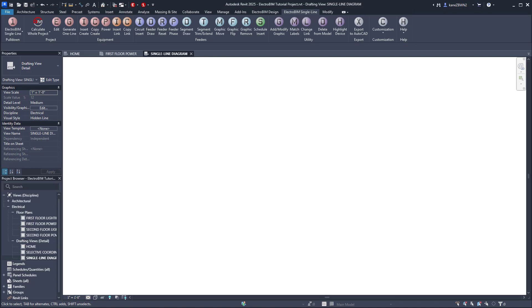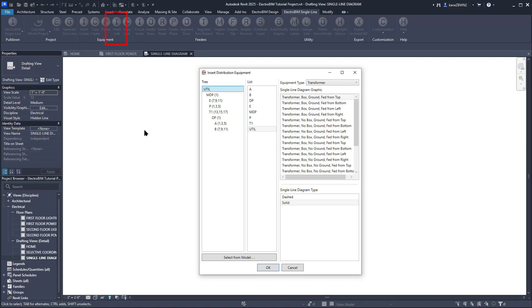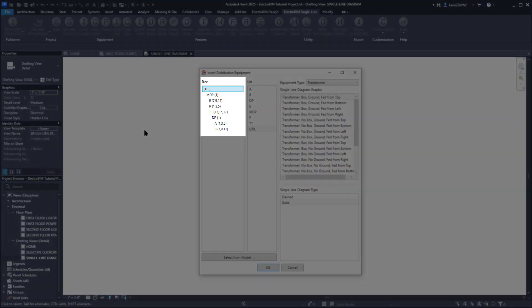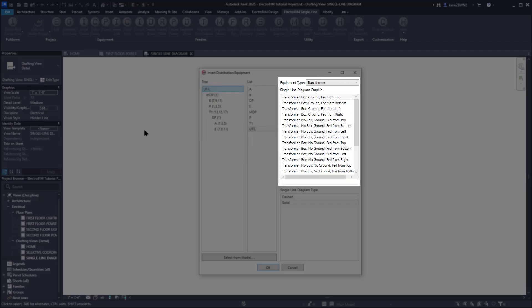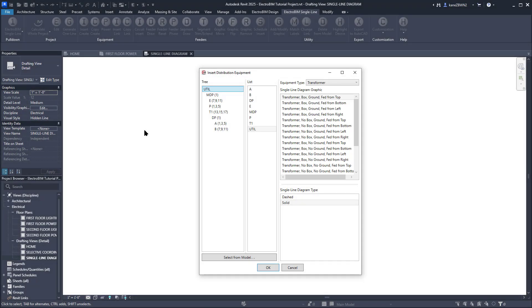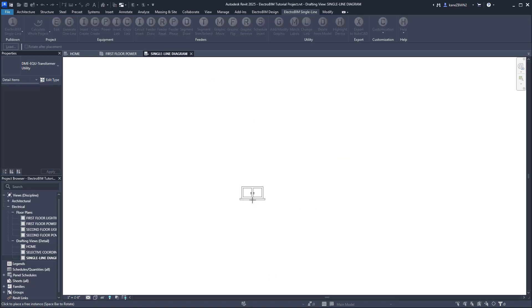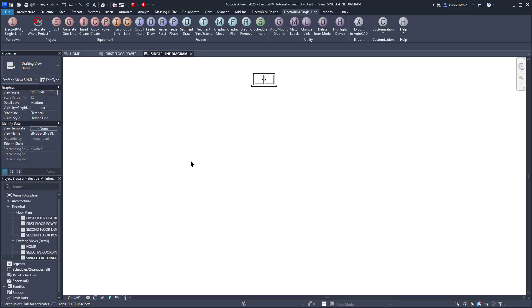We'll start by running the Insert Link command. This command allows you to select a device that already exists in your model and insert a corresponding graphic on the single line. We'll start from the top of our distribution tree, the utility transformer we've named Util. Because it's configured in Revit as a transformer, Electro BIM knows to give us transformer graphics to pick from. The graphics themselves and these lists are fully customizable. We'll go with the Utility Transformer graphic and press OK to insert it on the drafting view. Simply pick a spot, left click, and the graphic will be inserted.